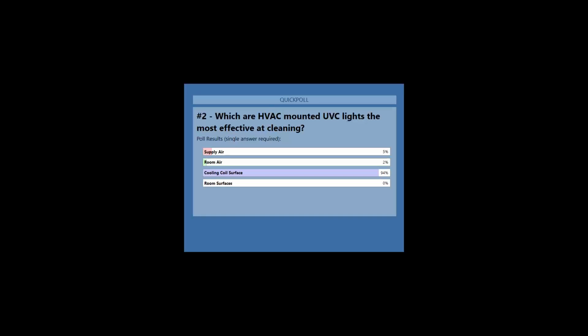So it's really good at cleaning the coil surface. Will it kill stuff in the supply air? Sure, but minimally. Return air? Sure, but minimally. Room air? Sure, but minimally. Room surfaces? Yeah, UV light's actually really good at killing germs on room surfaces, but not HVAC UV lights.